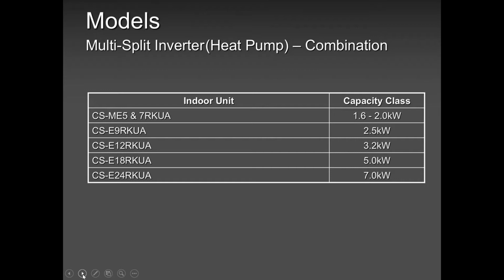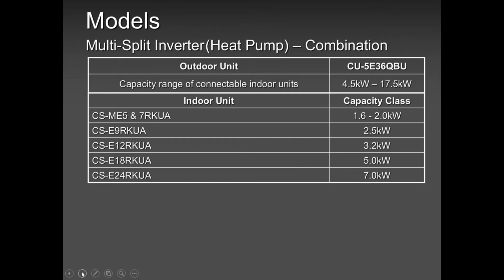Now, when I say a minimum of 2 indoor units is important, it doesn't mean any 2 indoor units, guys. You have to connect 2 indoor units that will total more than 4.5 and less than 17.5 kilowatts. If you don't obey this minimum and maximum capacity, you will have an H12 or H14 error code, mostly H12. It's a capacity error code. For example, the guy installed 2 7,000s. See what happened here? He ended up with 4 kilowatts, and what we need here is more than 4.5 kilowatts, 4.5 or more.